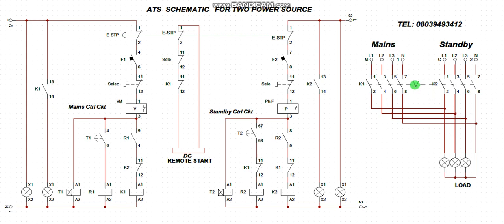Now this is an interlock device to interlock these two particular contactors. When this contactor is energized, this one will be disabled. When this one is energized, this one will be disabled. Any of the two that is being energized, my output is here, so I use this pilot lamp to illuminate the load symbol. Any of these two that is being energized, I will have output here. So this is my load to the supply to the house or to the factory.